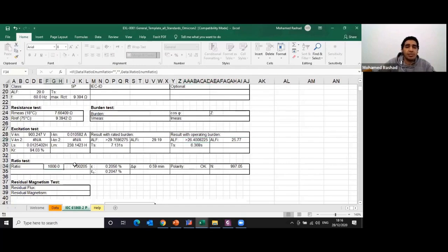Okay, and the ratio is 1000 to 1. Okay. And your error was 0.2%. Okay. And your angle. The angle is approximately half a minute, which is roughly okay. Is that all right? Understood.